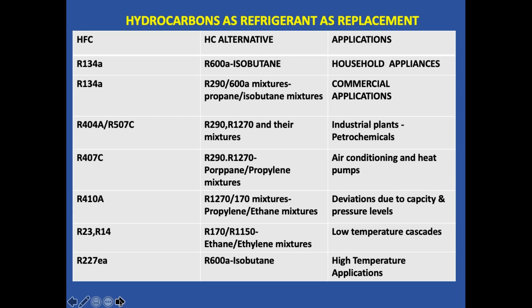R227 can be replaced by isobutane for high temperature applications. For every application, you will see there is a hydrocarbon available. Hydrocarbon as a refrigerant has been used in more than 300 million domestic refrigerators.